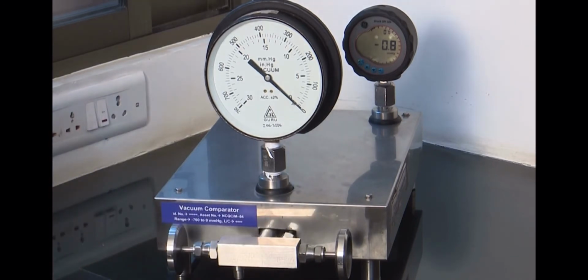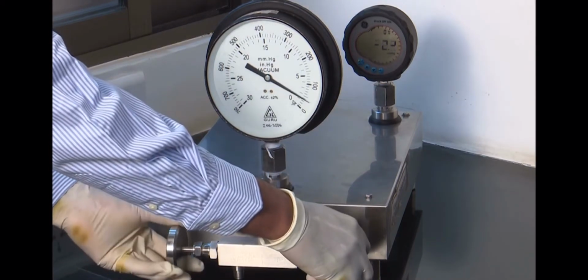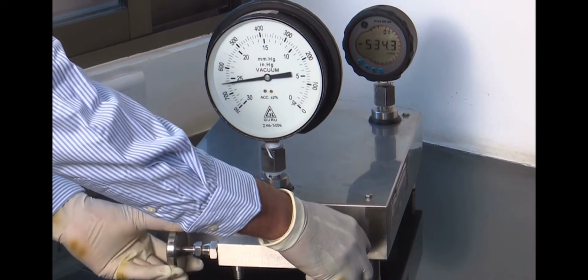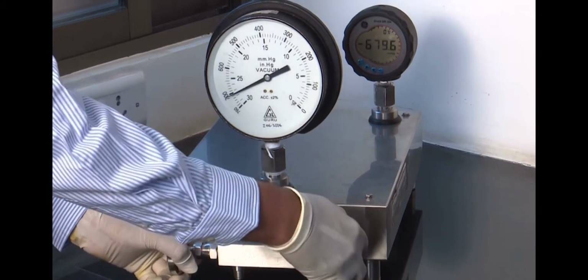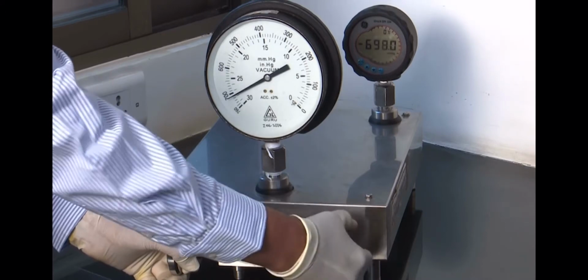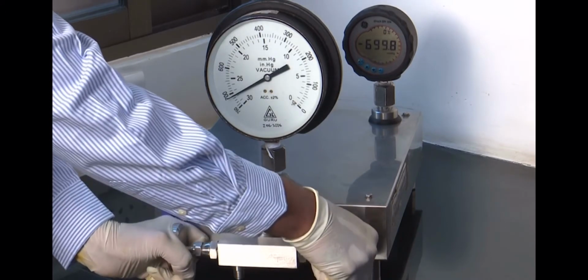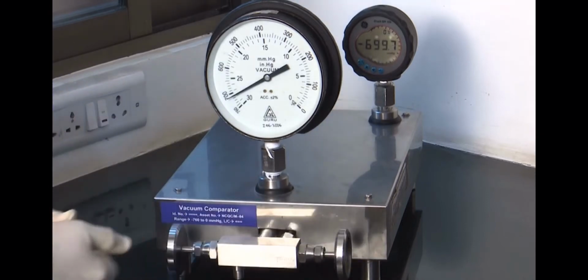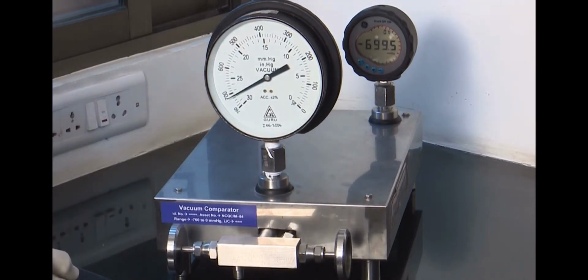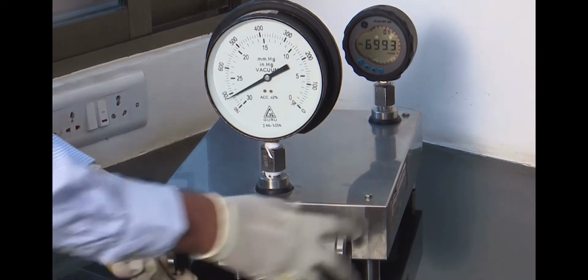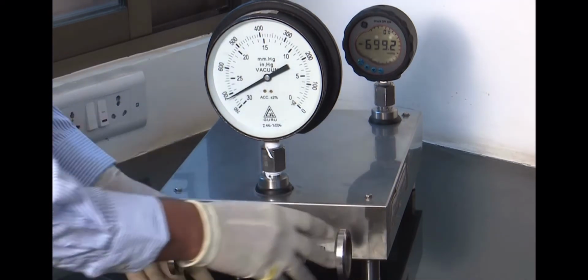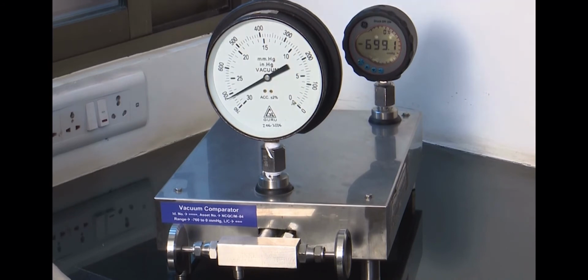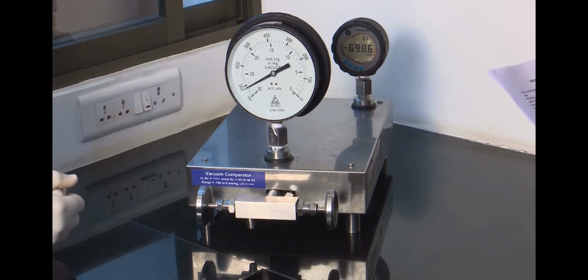First of all, I will perform leak test. Open the regulating valve of vacuum comparator to raise vacuum. Now I am operating it till full range, means it is open till maximum negative pressure on UUC is achieved. I am performing leak test at maximum negative pressure on UUC. So I will hold it for 2 minutes at maximum negative pressure to check leaks if any. Here no leakage is found, so we will proceed for preloading.